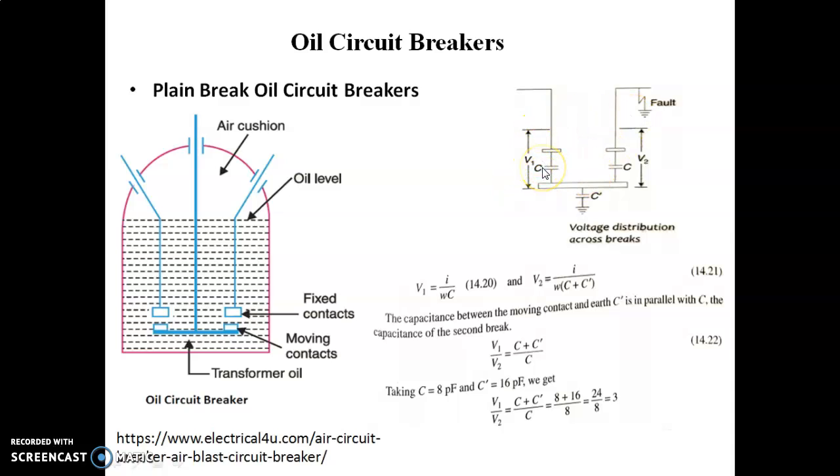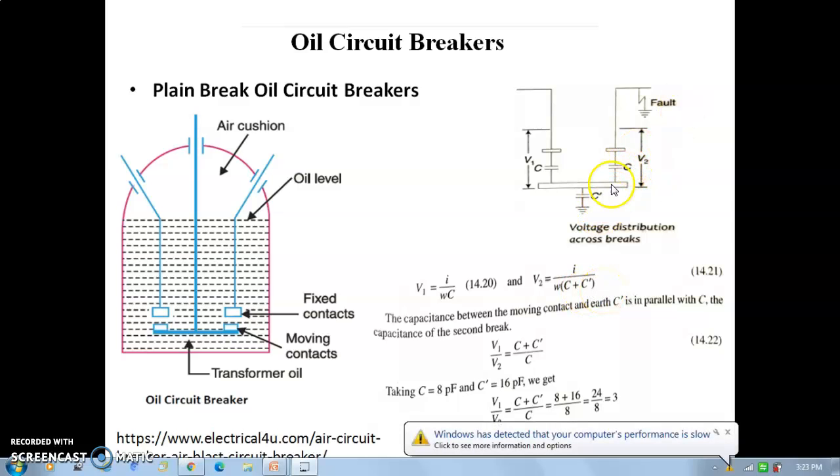The capacitance C is between the fixed contact and the moving contact, and C dash is between the moving contact and earth. This is the fixed contact capacitance. One side voltage is V1 and here voltage is V2. C and C dash are connected in parallel. Therefore, we can write: V1 = I/(ωC), and V2 = I/(ω(C+C')). Because this is connected to earth, these two are in parallel. V1/V2 = (C+C')/C. This is the voltage distribution across the breaks.